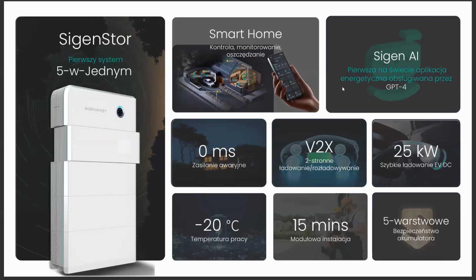Backup power, true 0 milliseconds transfer time. Finally, one parameter that clearly differentiates us from standard backup systems. Transfer time is exactly 0 milliseconds. How is this achieved? Our sine wave is synchronized and maintained slightly ahead of the grid sine wave phase, so the system remains in continuous readiness. This is not just a theoretical claim. I have personally verified it in previous work using a professional oscilloscope and power analyzers.